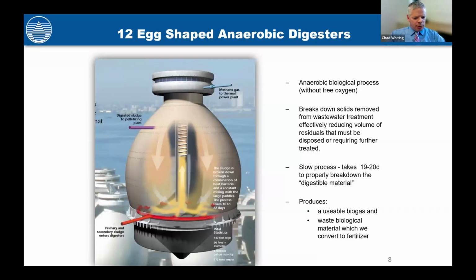We feed about 1.2 million gallons of thickened sludge to the digesters daily in a semi-continuous process. 5,000 gallons per digester, 1 digester at a time, alternating through 4 digesters in each mod. So we have 4 digesters in each mod. We have 3 mods of digesters. We get about a 20-day detention time at this flow rate. We monitor the volatile acids, the alkalinity, and the phosphorus levels.